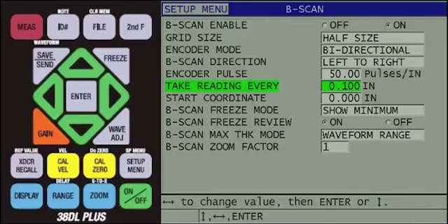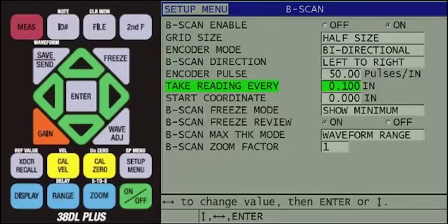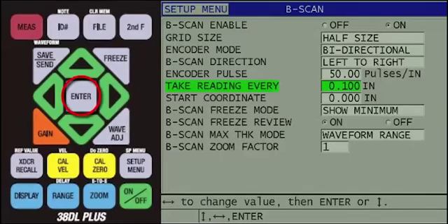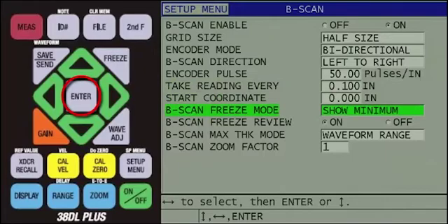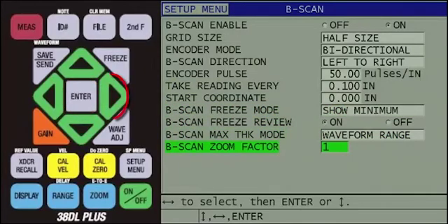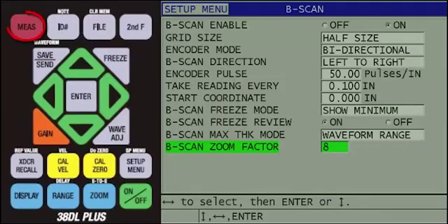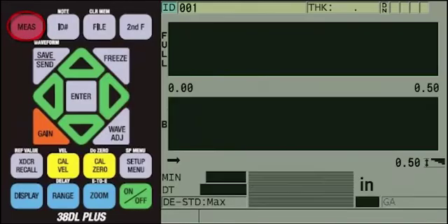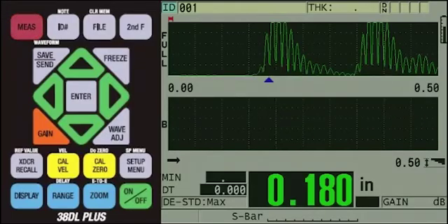The only other setting we will change is the B-Scan Zoom Factor. As discussed previously, an encoded scan with a zoom factor of 1 will yield a very compressed B-Scan. To change this, keep pressing the Enter key until B-Scan Zoom Factor is highlighted, then keep pressing the right arrow to change it to 8. You can then press the red Measure key to return to the Measurement screen.